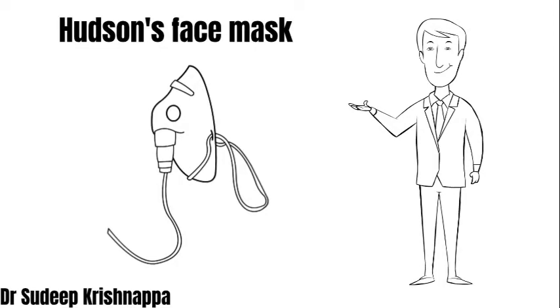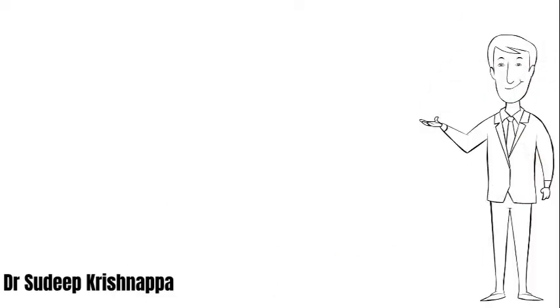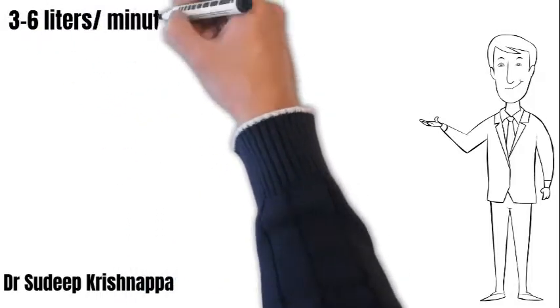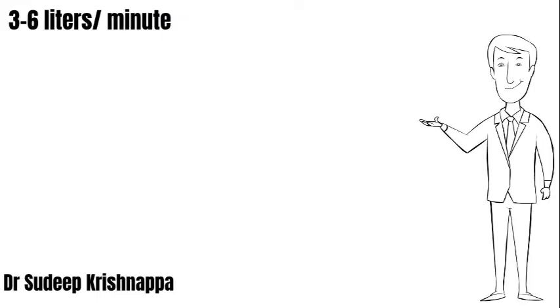Over the course of the next few minutes, we will be talking about Hudson's face mask with regards to what is the minimum flow needed — whether it's an arbitrary number or if there is a rationale behind it. We will also be talking about the effect of altering the fresh gas flow on two of the most important parameters: rebreathing and the variation in the inspired oxygen concentration. The rationale behind setting the minimum flow is to minimize or reduce rebreathing.